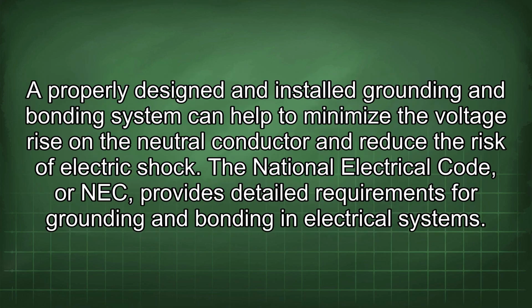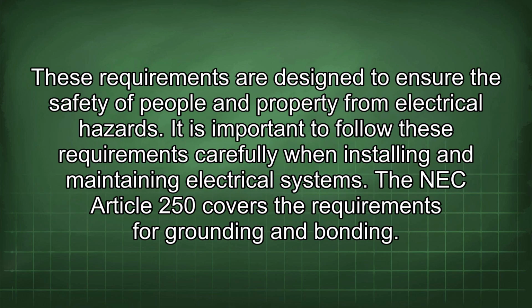A properly designed and installed grounding and bonding system can help to minimize the voltage rise on the neutral conductor and reduce the risk of electric shock. The National Electrical Code, or NEC, provides detailed requirements for grounding and bonding in electrical systems. These requirements are designed to ensure the safety of people and property from electrical hazards. It is important to follow these requirements carefully when installing and maintaining electrical systems.